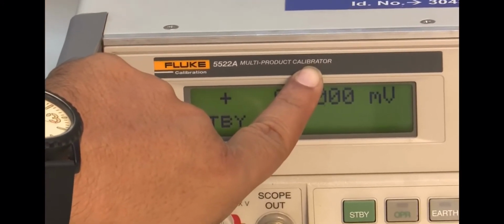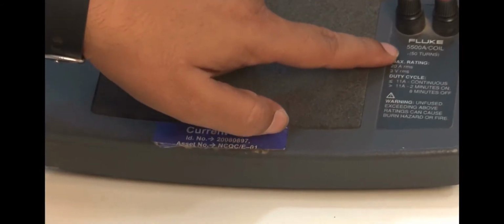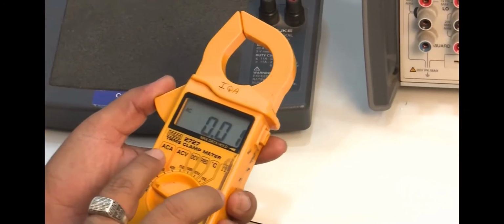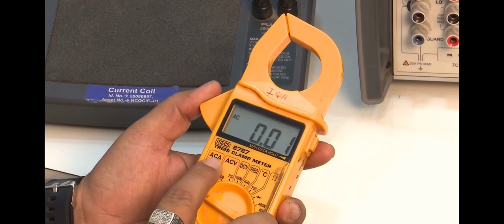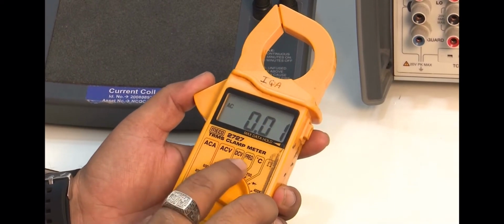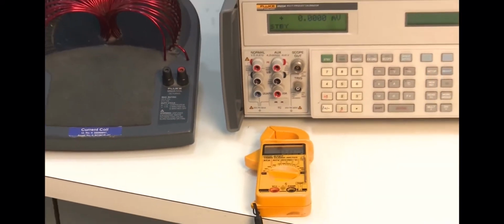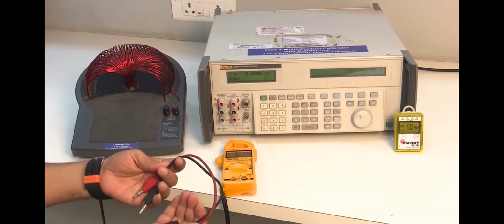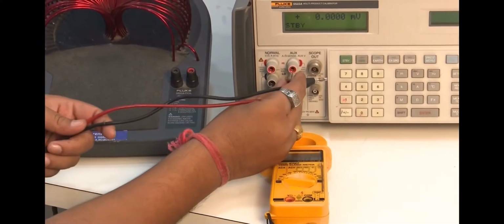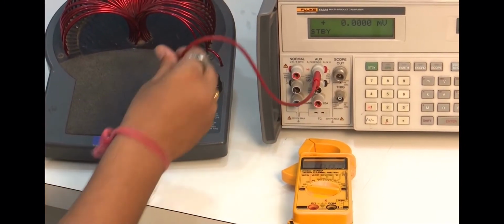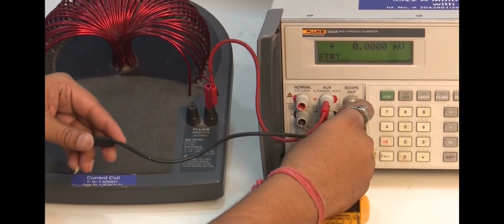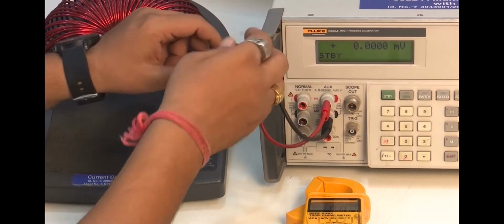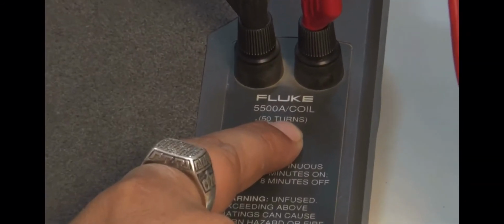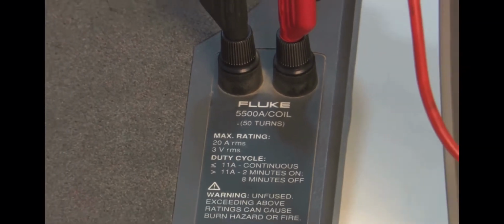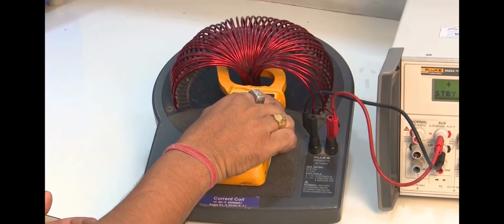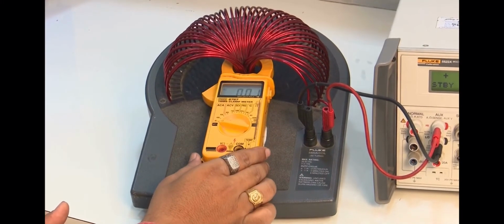For calibration, I am using multi-product calibrator with current coil as a reference instrument. I will calibrate the digital clamp meter for 4 parameters including AC-DC volt, AC-DC ampere, resistance and frequency measurement. I have selected an appropriate cord and connector. Connect the current coil, 50 turns, to multi-product calibrator. Place the clamp meter after opening its clamp inside the current coil and then keep it on the current coil in the clamped position.